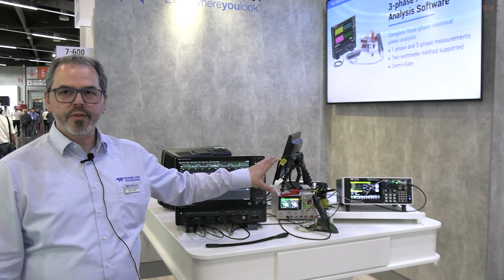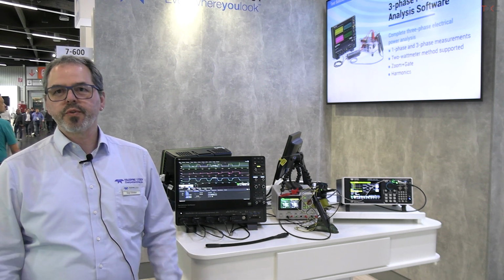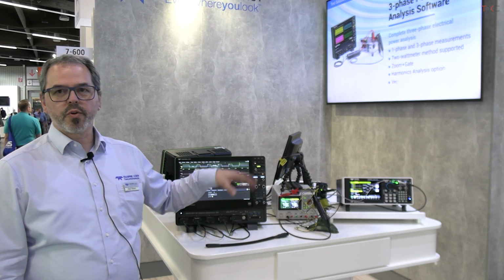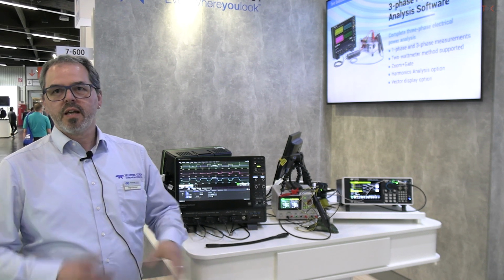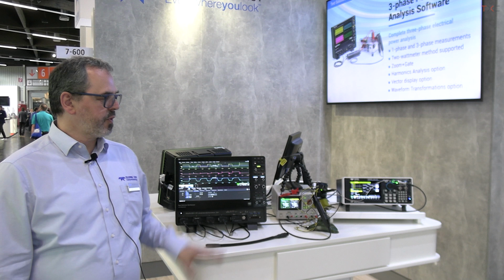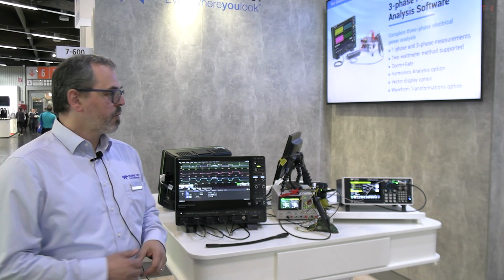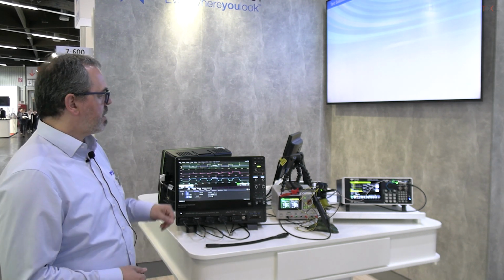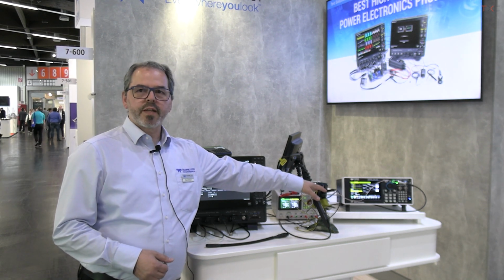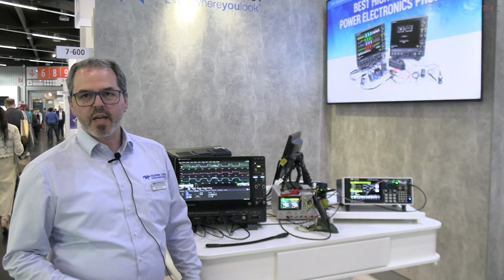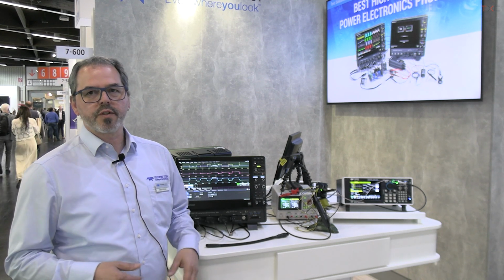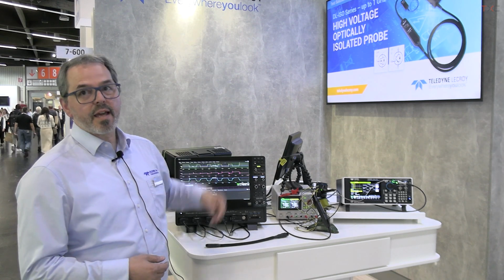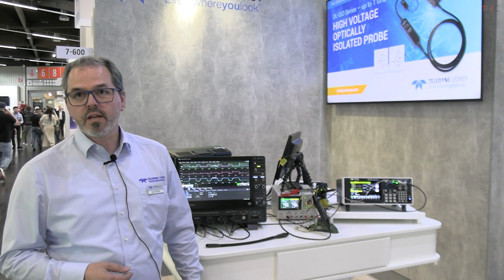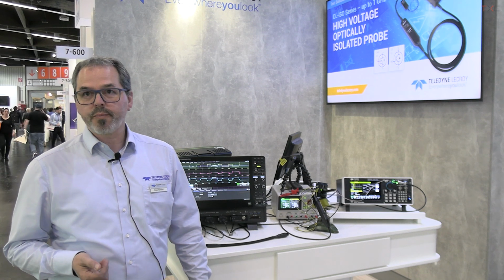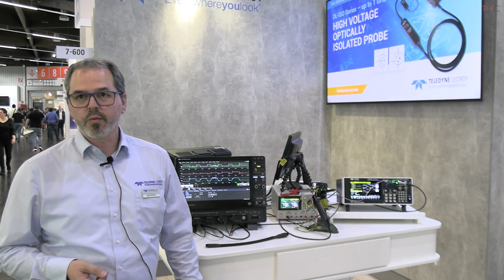We have here a small board, a demo board we use for showing these measurements, and we can control the board using the generator, and then we measure the signals at the board, at the switching device, with the instrument. For measuring, we have different probes in that setup. We have one small probe, a differential probe, the DL-HCM, where we can measure the low side gate. It goes up to 1 GHz of bandwidth. Then for the high side gate, we have the optically isolated probe, the DL-ISO, which goes up to 1 GHz of bandwidth and up to 2.5 kilovolts.